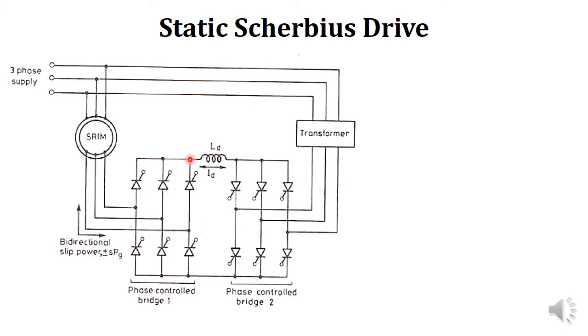The basic concept of the static Scherbius drive is that it allows the flow of slip power in both directions. In the case of a static Kramer drive, the slip power flows from the rotor through the converters, through the transformer, and back to the power supply — that was the only direction. But the static Scherbius drive allows slip power to flow both from motor to supply mains and from supply mains to motor.